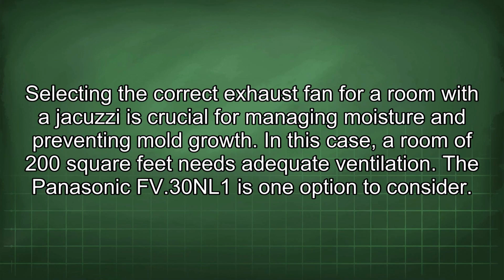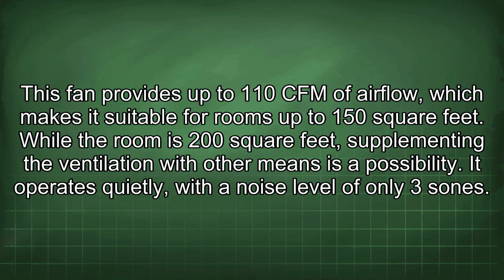Selecting the correct exhaust fan for a room with a jacuzzi is crucial for managing moisture and preventing mold growth. In this case, a room of 200 square feet needs adequate ventilation. The Panasonic FV-30NL1 is one option to consider. This fan provides up to 110 cfm of airflow, which makes it suitable for rooms up to 150 square feet. While the room is 200 square feet, supplementing the ventilation with other means is a possibility.